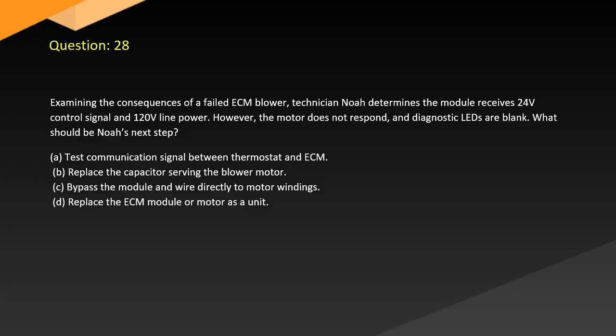Question 28. Examining the consequences of a failed ECM blower, technician Noah determines the module receives 24 V control signal and 120 V line power. However, the motor does not respond and diagnostic LEDs are blank. What should be Noah's next step? A. Test communication signal between thermostat and ECM. B. Replace the capacitor serving the blower motor. C. Bypass the module and wire directly to motor windings. D. Replace the ECM module or motor as a unit.